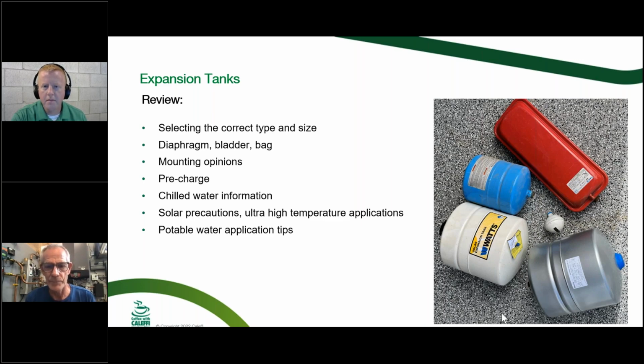But I think the butyl EPDM is, pump gaskets, a lot of things are made out of EPDM. That seems to be the go-to material for seals in hydronics, but I'm not sure. And like I said, some of them now are saying they've got an antimicrobial. I don't know if that's built into the bladder or where that is in the tank, but I don't want to give you bad advice and say, yeah, it's fine to do that. I would check with whatever brand tank you're going to use, but I know people have used them on non-barrier tube systems and get better results than the plain steel.